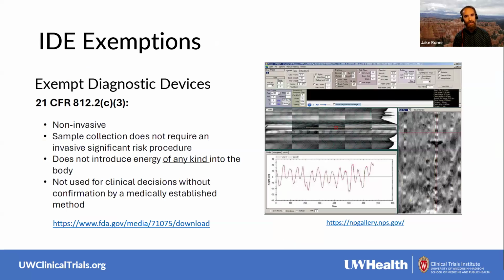Jumping to the other big IDE exemption, it's exempt diagnostic devices. Again, the regulatory citation is there. So this applies to devices that are non-invasive, do not require invasive sampling, do not introduce energy of any kind, and are not used for clinical decisions without confirmation by a medically established method. More often than not, we think about these in terms of in vitro diagnostic devices, so assays, tests, particularly when you're not releasing the results of that testing. But it isn't limited to that.